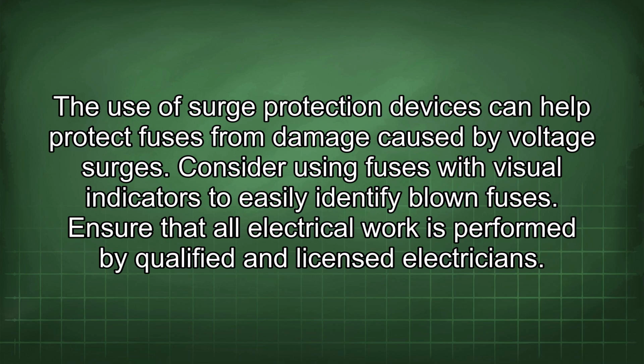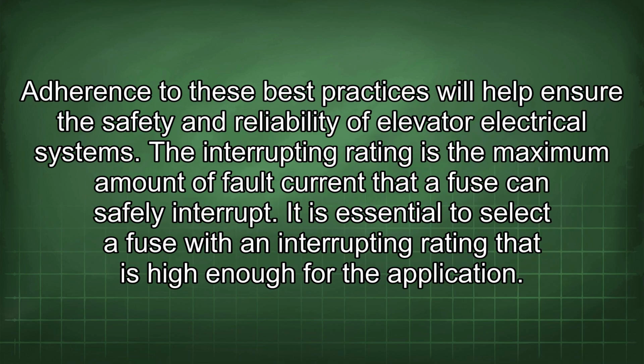Consider using fuses with visual indicators to easily identify blown fuses. Ensure that all electrical work is performed by qualified and licensed electricians. Adherence to these best practices will help ensure the safety and reliability of elevator electrical systems. The interrupting rating is the maximum amount of fault current that a fuse can safely interrupt. It is essential to select a fuse with an interrupting rating that is high enough for the application.